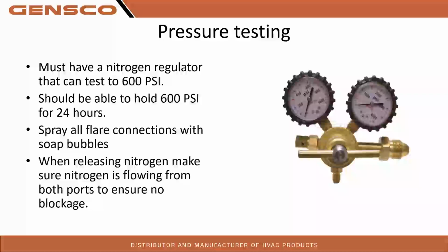Generally what I recommend for guys is, 600 PSI pressure test, absolutely every single time, no question about that. Or is the 24 hours, like I said, if you can get at least a couple hours of pressure test on there, go through, spray all your fittings with soap bubbles, make sure you have no leaks. And if you've verified no leaks on your fittings and you're able to hold 600 PSI for a couple hours, then chances are you're going to be okay. I would probably be all right with that if it was my job, just because, like I said, 24 hours, I don't think any of us would get any bids if we actually did that. If you can do it, that's a 2-day job. I'd highly recommend you do.